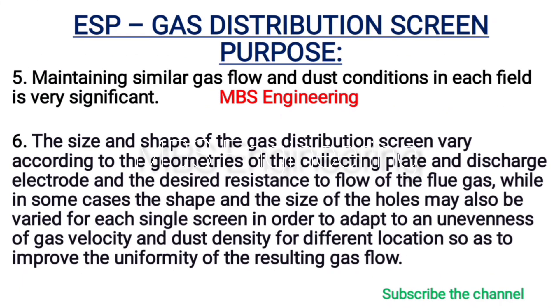Point 5: Maintaining similar gas flow and dust conditions in each field is very significant. Point 6: The size and shape of the gas distribution screen vary according to the geometries of the collecting plate and discharge electrode and the desired resistance to flow of the flue gas. In some cases, the shape and size of the holes may also be varied for each single screen in order to adapt to unevenness of gas velocity and dust density at different locations, so as to improve the uniformity of the resulting gas flow.